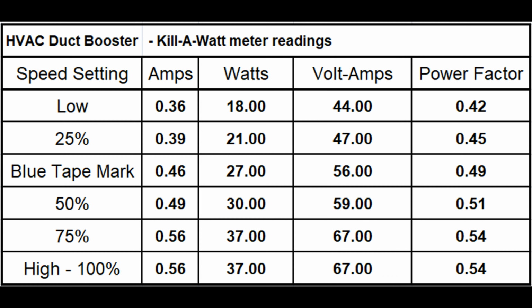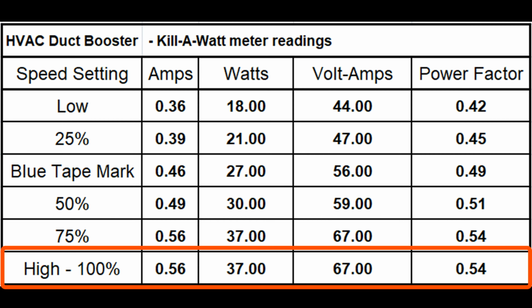These are all the readings I took, but I really only need the high-speed current for sizing the motor circuit fuse. So I'm using 0.56 amps. Why is that so different from my first calculation of 0.308 amps? Let's explore the topic of power factor a little bit. This should give us enough information to understand what's going on.